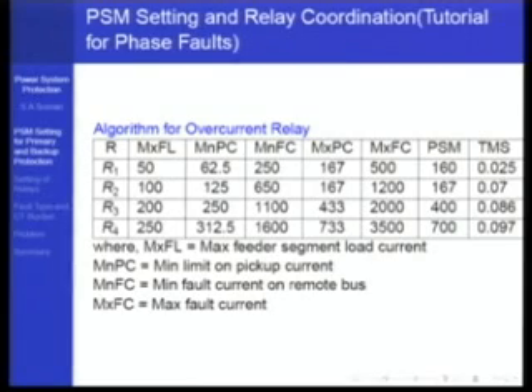So that means for setting R1 there is a big range for deciding the pickup current in this example, from 62.5 amperes to 167 amperes. And the maximum fault current is 500, so you don't have to worry about that. Maximum fault current is always above the minimum fault current. So let us say that we decide, since we have a lot of choice, that we will set the pickup current to 160 amperes.